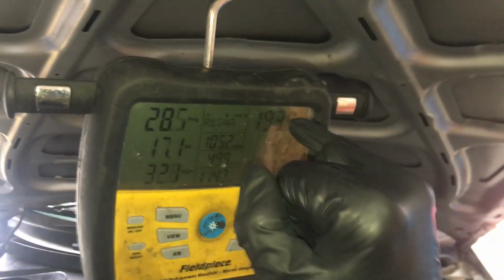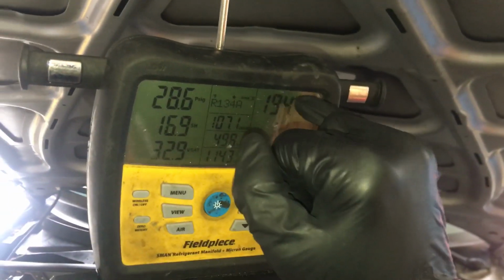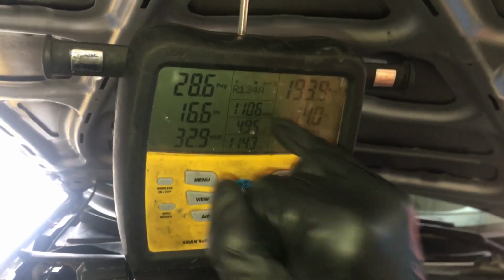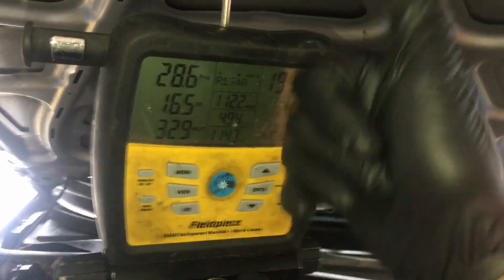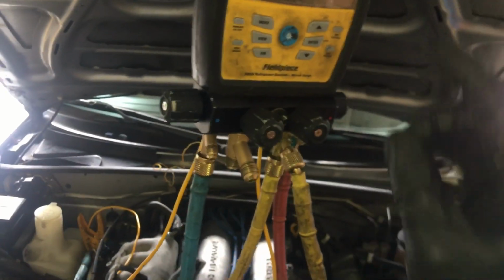You'd have the sun hitting the top, making the top hot, and all that would put more heat load on top of the evaporator. So what you would see is a much higher level of pressure, your suction line temperature would go up, your liquid line temperature would go up. So your supply temperature, everything would go up if this was in the real world.